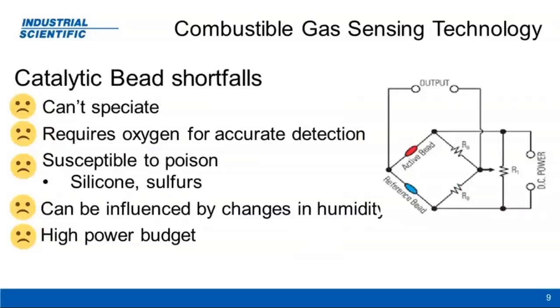One of the biggest downfalls of catalytic bead technology is that it requires oxygen for accurate combustible detection. It's not a limit of the technology per se, it's a limit of physics. Stoichiometrically speaking, you need 10% oxygen to detect, burn, and catalyze 5% methane. It's as simple as that. The sensors require oxygen, and below a certain oxygen limit, which differs for every sensor, detection is certainly limited.